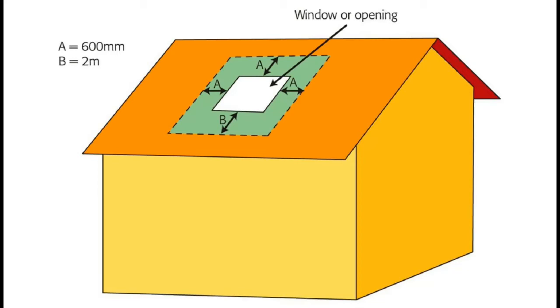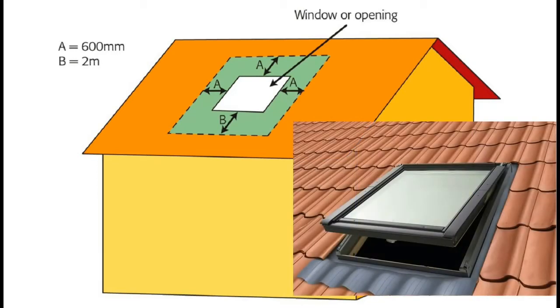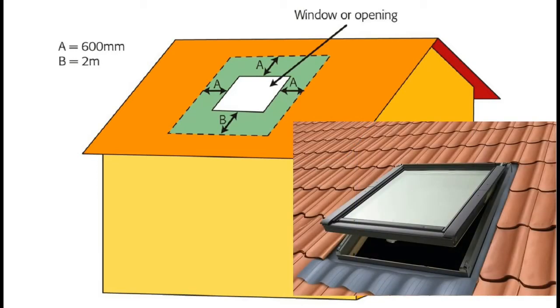In reality a Velux window looks like that. In this diagram it shows you that you cannot place a terminal nearer to that window than 600 millimetres horizontally to the side or 600 millimetres above it.